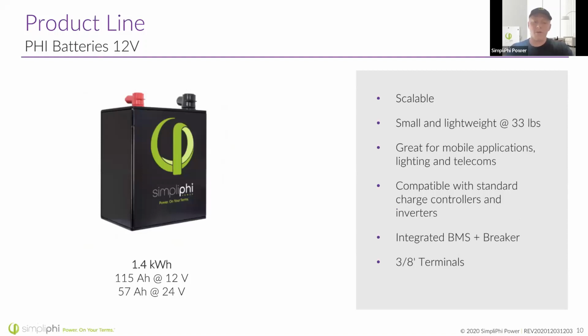We also offer a very similar product in a smaller size. So this is a 1.4 kilowatt hour coming in 12 volts or 24 volts. This battery now does have a breaker integrated and terminals on the top. It's scalable, so really with this and with the 3.8, you can parallel as many as you need. I've seen people parallel up to 100 of these batteries.